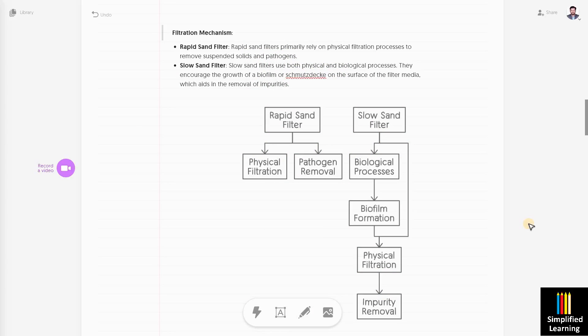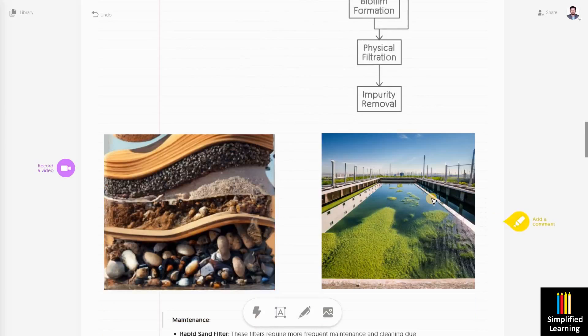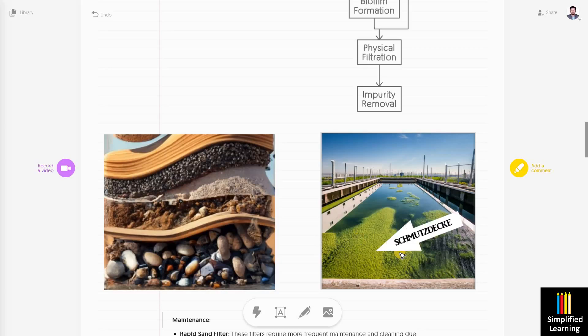When we talk about mechanism, rapid sand filter totally relies on the physical filtration process — a granular bed filters impurities from raw water and the filtrate is clean water. Slow sand filter makes use of both physical filtration and biological filtration. When water passes through a slow sand filter, it develops a biofilm growth called a schmutzdecke. As you can see in the diagram, a green dirty layer forms in a slow sand filter, and this film filters water more efficiently.